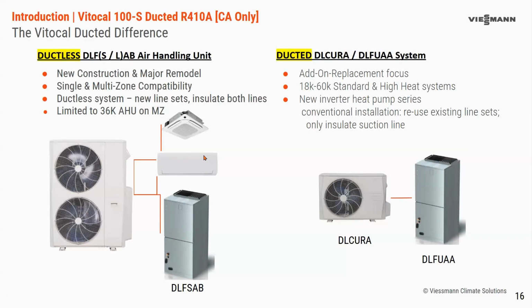Okay, we're getting close to the end here. One question that may come up, or a distinction to be made, is the difference between the ductless air handler and the ducted air handler. There are two different model numbers on the air handler, so you don't want to mix those up. The ductless, really the largest use case would be in a multi-zone application where you want a mix of ducted and ductless. You can do a single one-to-one air handler with ductless. However, with the line sets and the 24-volt interface, it is a better solution to use the central ducted system on a one-to-one basis. And with a multi-zone, you're limited to only 36,000 BTU maximum size, whereas with the central ducted, you can go up to 5 tons.